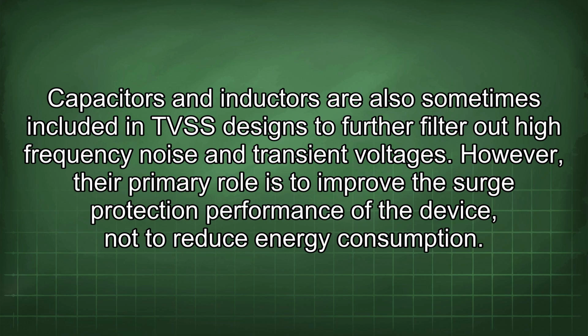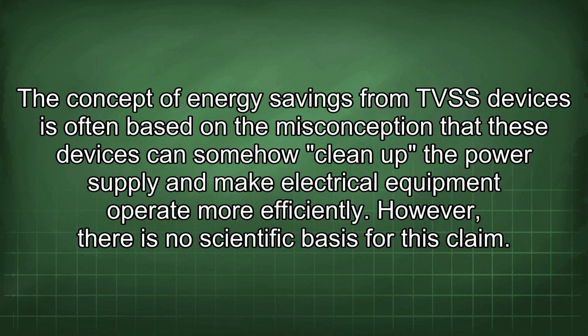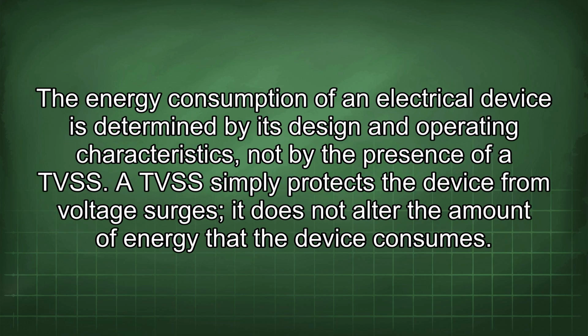Capacitors and inductors are also sometimes included in TVSS designs to further filter out high-frequency noise and transient voltages. However, their primary role is to improve the surge protection performance of the device, not to reduce energy consumption. The concept of energy savings from TVSS devices is often based on the misconception that these devices can somehow clean up the power supply and make electrical equipment operate more efficiently. However, there is no scientific basis for this claim. The energy consumption of an electrical device is determined by its design and operating characteristics, not by the presence of a TVSS.